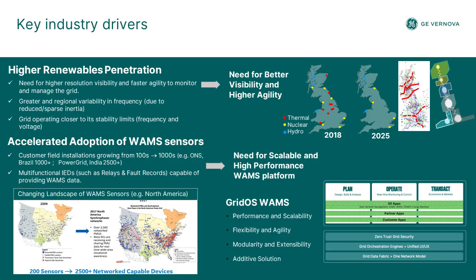The other aspect is that most of these renewable generation is inverter-based resources. And these inverter-based resources have sophisticated controls on them. And so the controls are known to create dynamics, and those controls can interact with the grid, destabilizing the grid potentially. We have seen what is called forced oscillations on the grid. So all of these physical characteristics of high penetration renewables requires greater visibility into the dynamics, which is what WAMS offers. And furthermore, the agility or the controls to be able to stabilize the grid should there be a need.